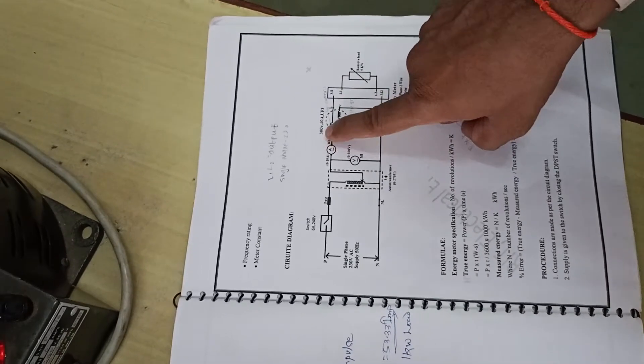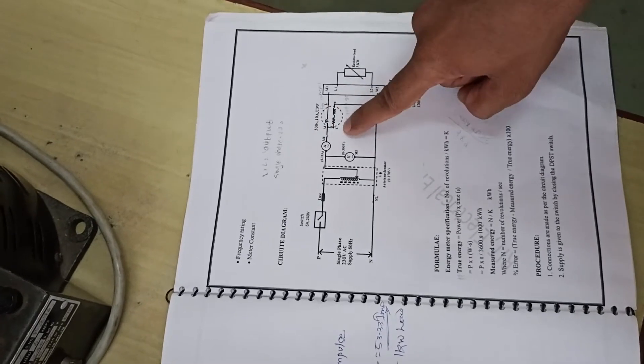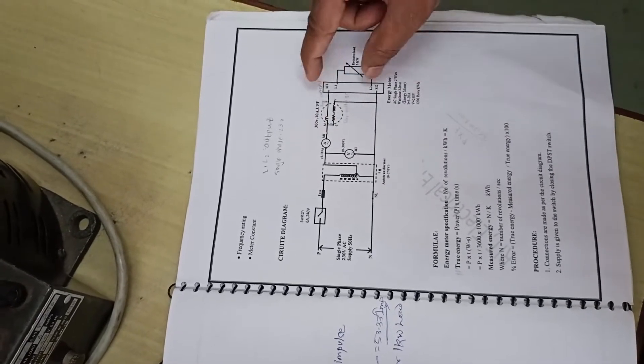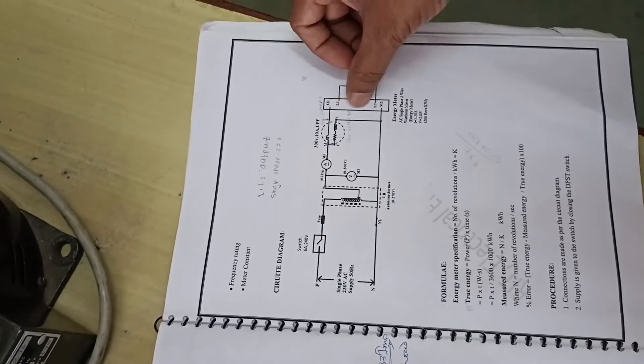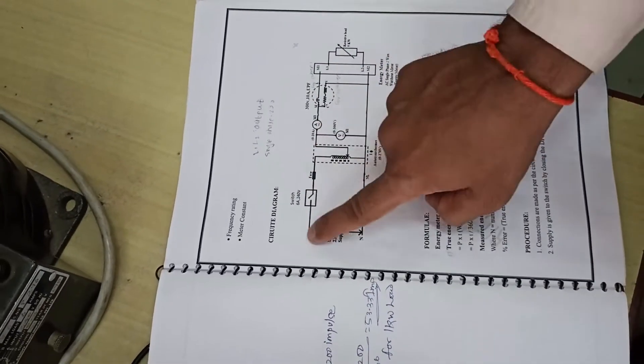In wattmeter we have 4 points M, L, C and V where M and C will be shorted. After that we have our energy meter with a resistive load of 5 kilowatt.